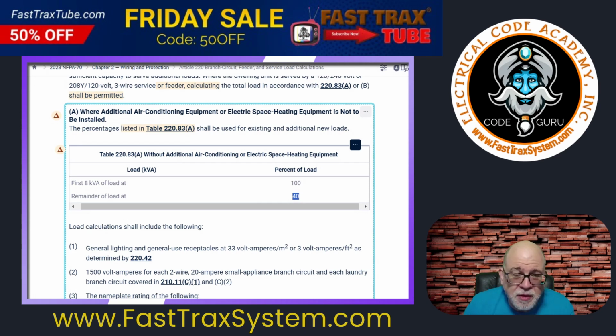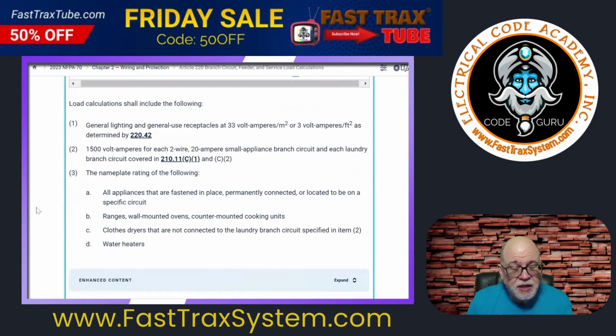This is pretty similar to what you get when you do the optional method for a single dwelling, right? The only difference is here it's the first 8,000, whereas in the optional method it's the first 10,000 and then the remainder at 40%. But here it's the first 8 at 100%. So that's really the only significant difference there. Now, when you're looking at that dwelling, it's existing or not. This is why I talked about at the beginning, maybe you just do a full calculation and see what it would be as if you were building this house new. But it's kind of the same concept.